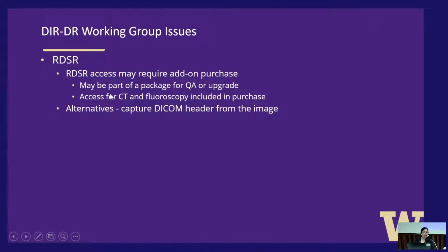However, the problem with X-ray, unlike CT, is that DICOM structured dose reports are very difficult. We have Shimadzu, and it doesn't give us entrance skin dose. I think it gives us DAP, which is really painful. Some systems, you cannot just get it with your system when you're buying equipment. It has to be a separate add-on purchase to have a DICOM structured dose report, which I think is ridiculous. It should be part of the equipment. Vendors really need to make it part of the equipment.